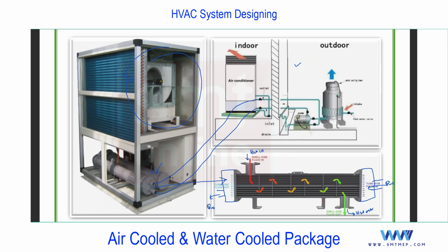When the refrigerant comes in, it will flow inside the tube, not in the shell. Since it's a condenser, the refrigerant comes in a hot state after compression. Now, we are supplying water, not chilled water, but normal atmospheric temperature water, or cold water I can say. When the cold water enters the shell, it will flow over the coils, and you can find partitions called baffles. So water comes in, flows like this, and goes out. The water is responsible for extracting the heat of the refrigerant. By extracting the heat from the refrigerant, condensation happens, and at the outlet the refrigerant is in the liquid state. You know the process.